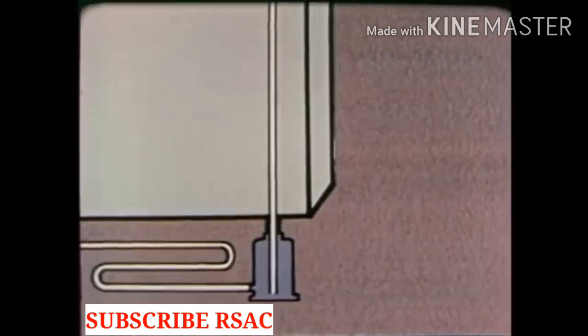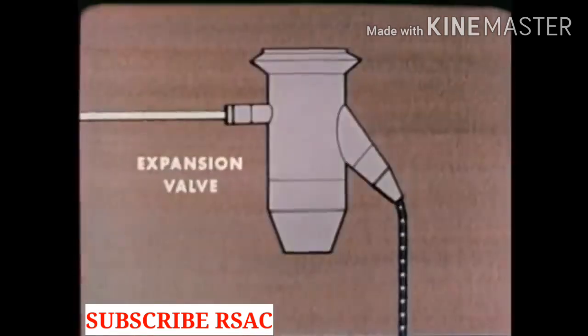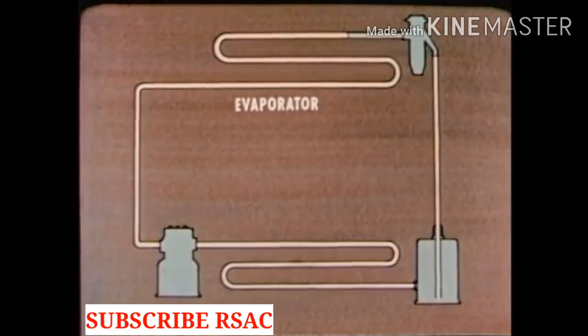Now let's see how a refrigerator works. We'll begin at the receiver where the excess refrigerant is stored. It is in the liquid state and under high pressure. The high pressure forces the refrigerant through the liquid line to the expansion valve. This valve causes a pressure drop. The high pressure liquid becomes a low pressure liquid. This is like letting air slowly out of a balloon. The air in the balloon is still under high pressure but the air that gets through expands and its pressure drops. In the same way refrigerant that passes through the expansion valve expands and its pressure drops. The low pressure refrigerant flows into the evaporator.